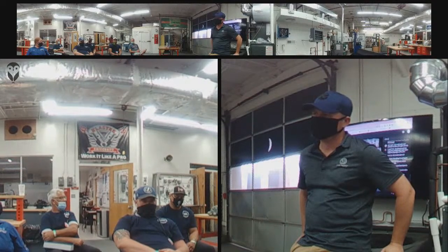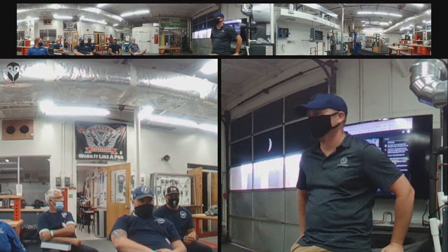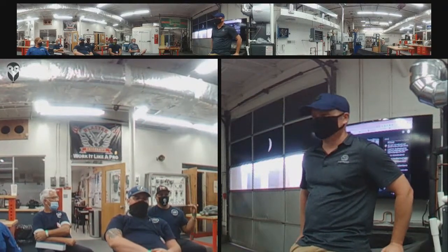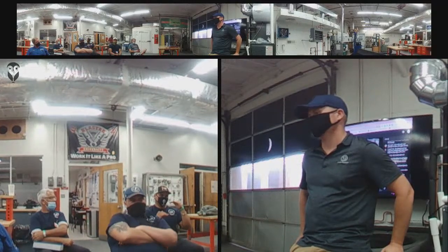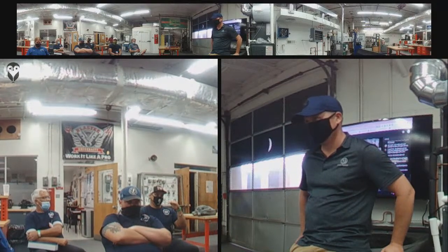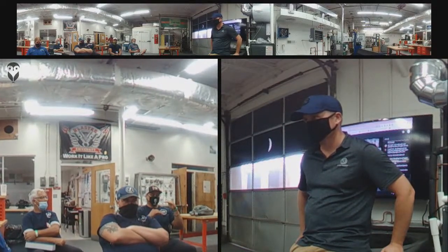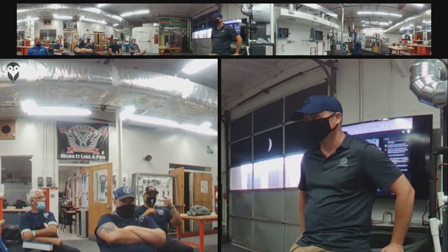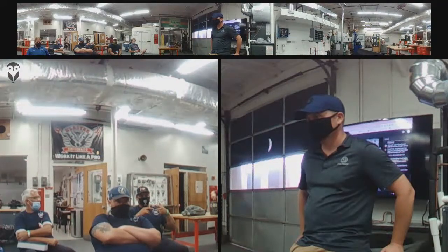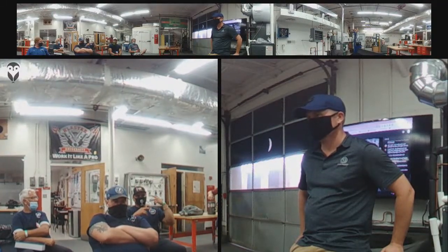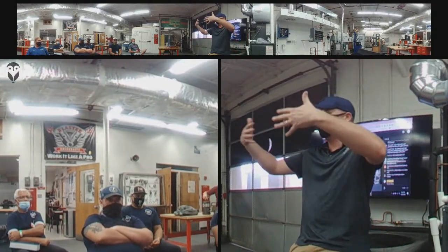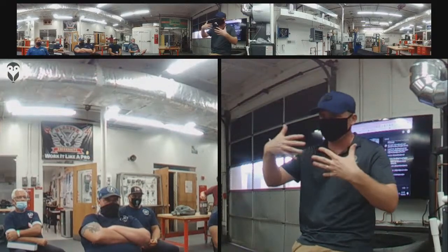So I started troubleshooting the equipment, and I found that they had a contactor for the condenser and another contactor for the blower, and they put the low voltage on the wrong one. So let's say the G wire that goes to the blower was going into the condenser. Oh, okay, right, because you have two control wires. Yeah, right. Let's pause here, because this is really good.